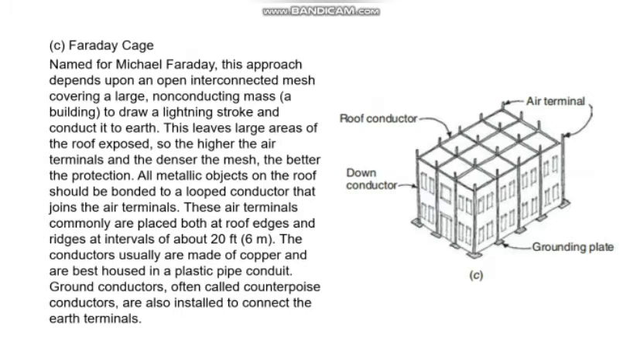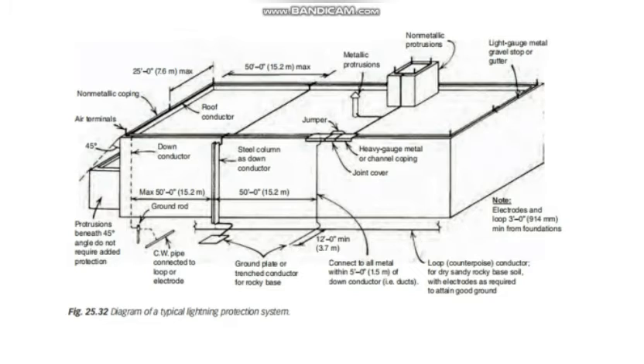The conductors usually are made of copper and are best housed in a plastic pipe conduit. Ground conductors, often called counterpoise conductors, are also installed to connect the earth terminals. This is a diagram of a typical lightning protection system. So, air terminals are commonly found at the roof edges, and if the building has a steel column, it can serve as a down conductor that connects the air terminals and the ground plate.